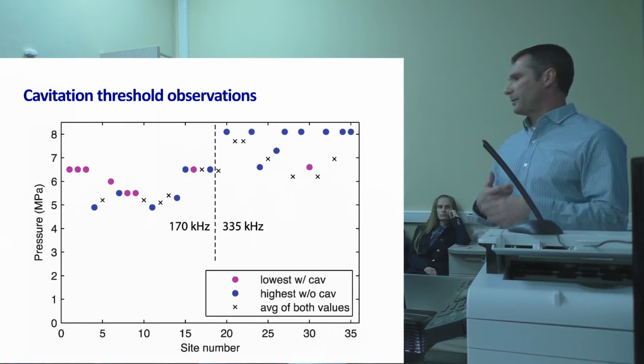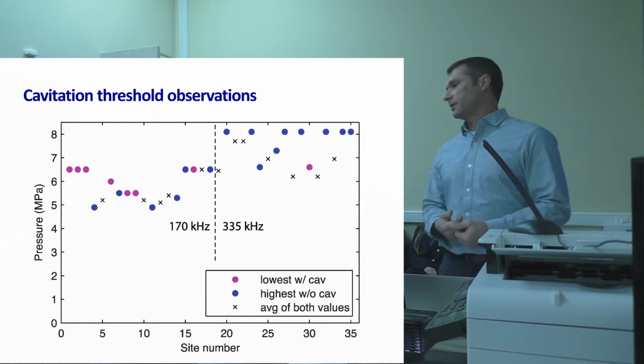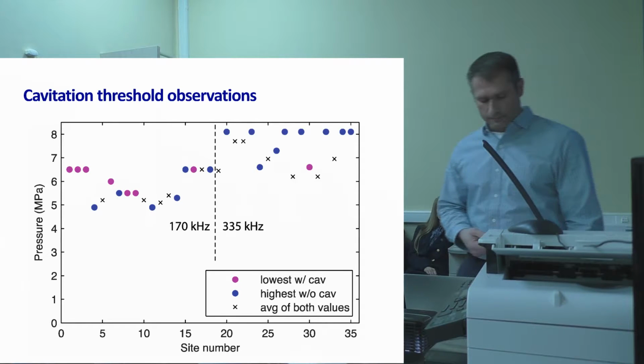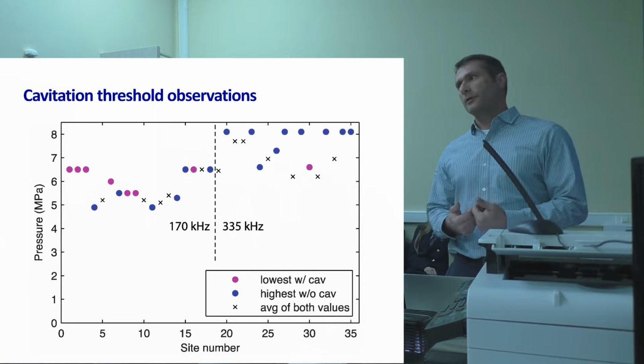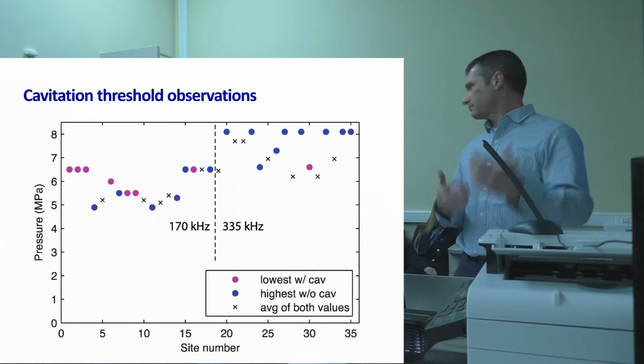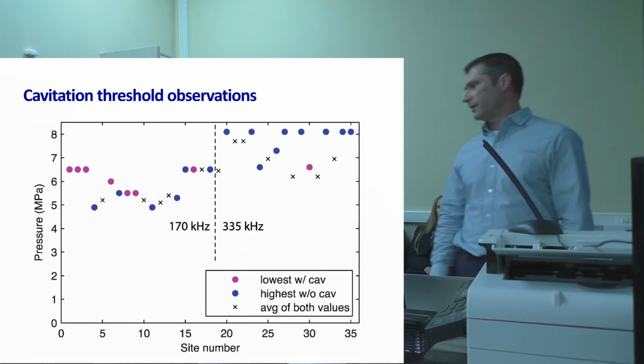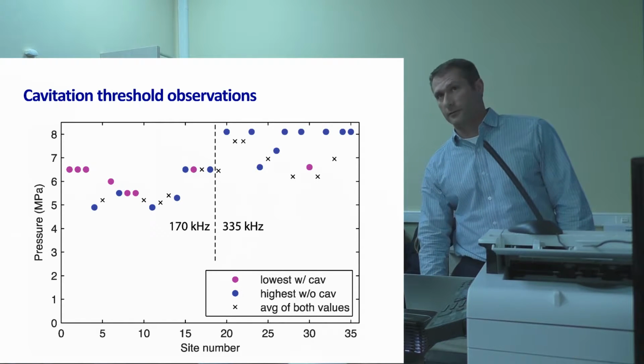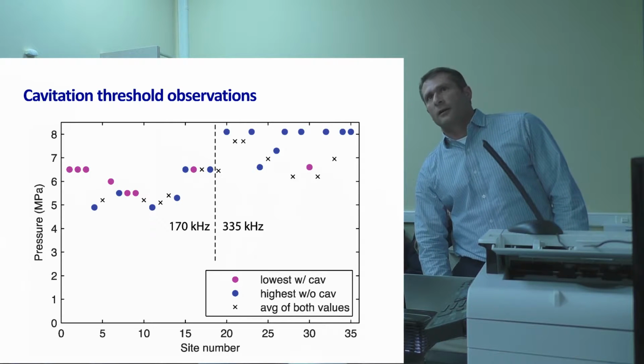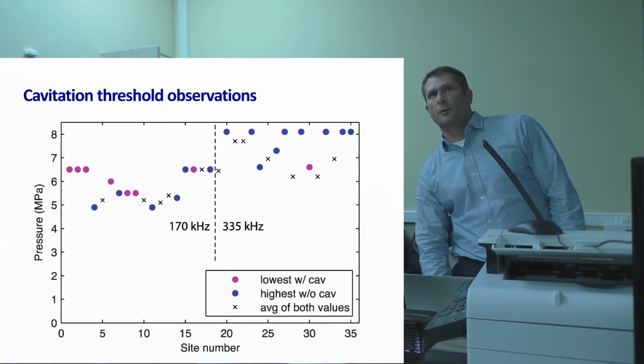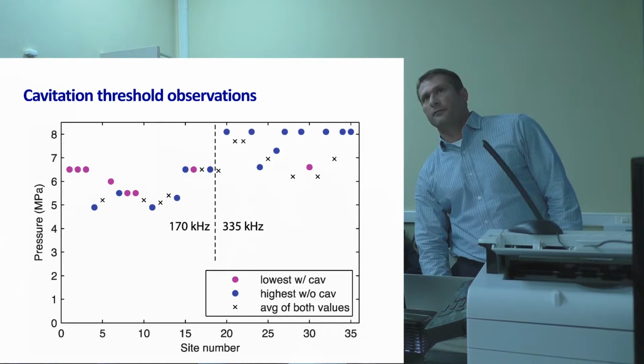So if you're trying to make a patient stone-free in a single treatment, you want to make all of your fragments approximately this size, and this is what we think we can control well with burst wave lithotripsy. So here, it should be higher than the blue circles. For all of these sites, we turned up, and this was as high as we can turn this current transducer. We never achieved cavitation.